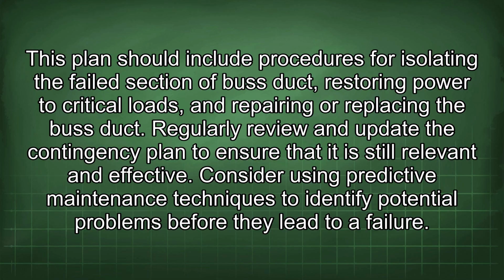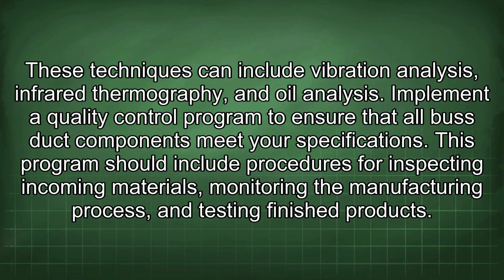Regularly review and update the contingency plan to ensure that it is still relevant and effective. Consider using predictive maintenance techniques to identify potential problems before they lead to a failure. These techniques can include vibration analysis, infrared thermography, and oil analysis. Implement a quality control program to ensure that all bus duct components meet your specifications. This program should include procedures for inspecting incoming materials, monitoring the manufacturing process, and testing finished products.